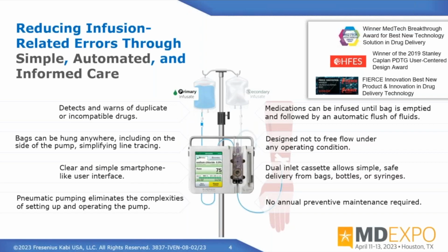And then I think the most impactful for this group is no annual preventative maintenance is required. So I talked about the calibrated chamber inside the device and the pneumatic technology. Because the system is calibrated and calibrates itself during every infusion, there's no need for it to be calibrated annually or checked for rate accuracy annually. And this was part of our 510(k) clearance with the FDA. Rather challenging to get through because it's a different way of thinking, right? We talked about new technologies and different ways of addressing issues in the market.